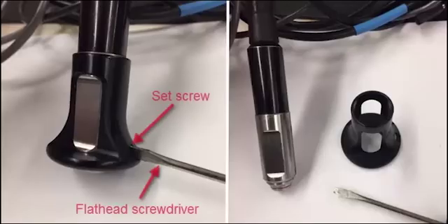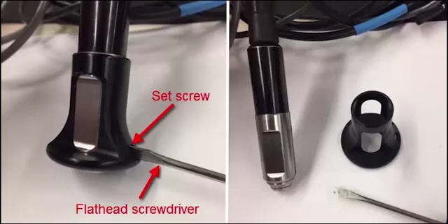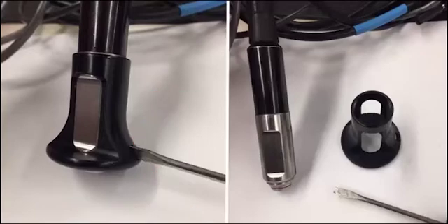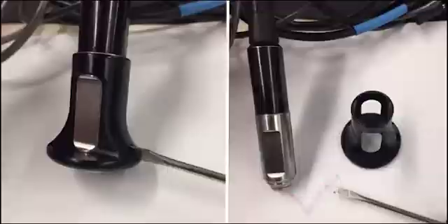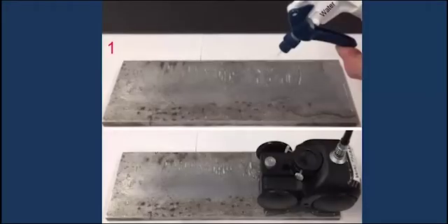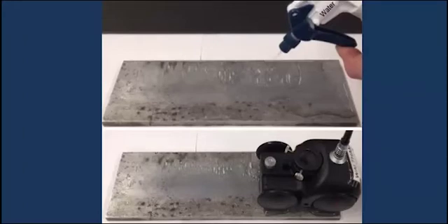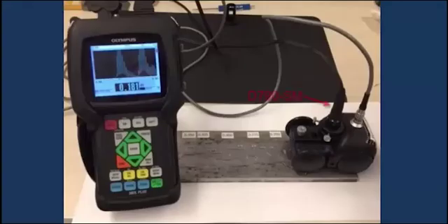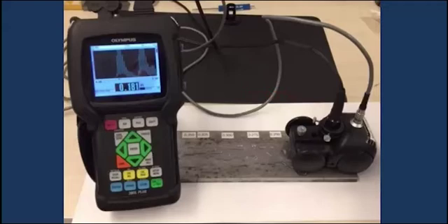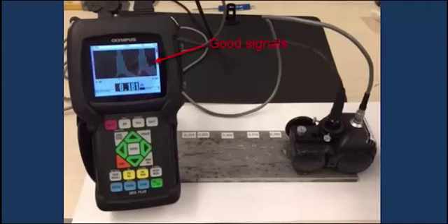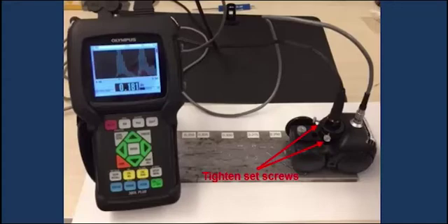Next, we will need to use a flathead screwdriver to remove the bell housing from the D-790-SM transducer so it can fit in the probe holder of the B-Scan buggy. Once the bell housing is removed, you can apply water to the surface of the aluminum sample and then place the buggy onto the aluminum plate. Loosen the two set screws on the probe holder enough to allow the D-790-SM to be inserted. Before tightening the two set screws, check the waveform display on the 38DL Plus to make sure you are getting good signals. If the signals on the waveform display look good, you can tighten the two set screws until they are holding the D-790-SM securely.